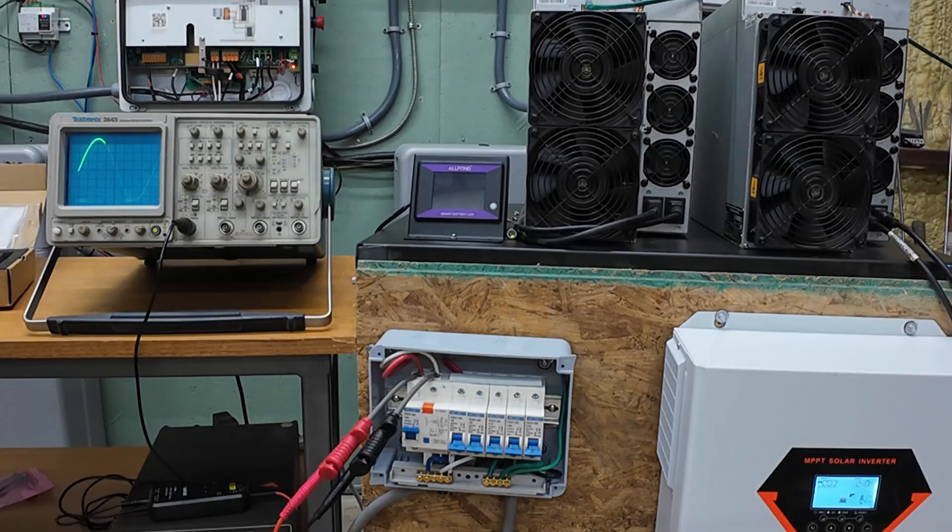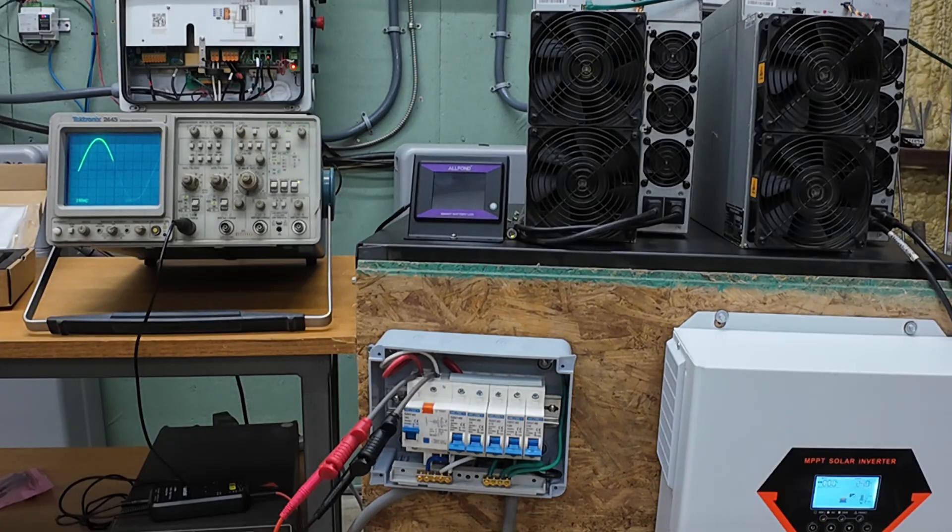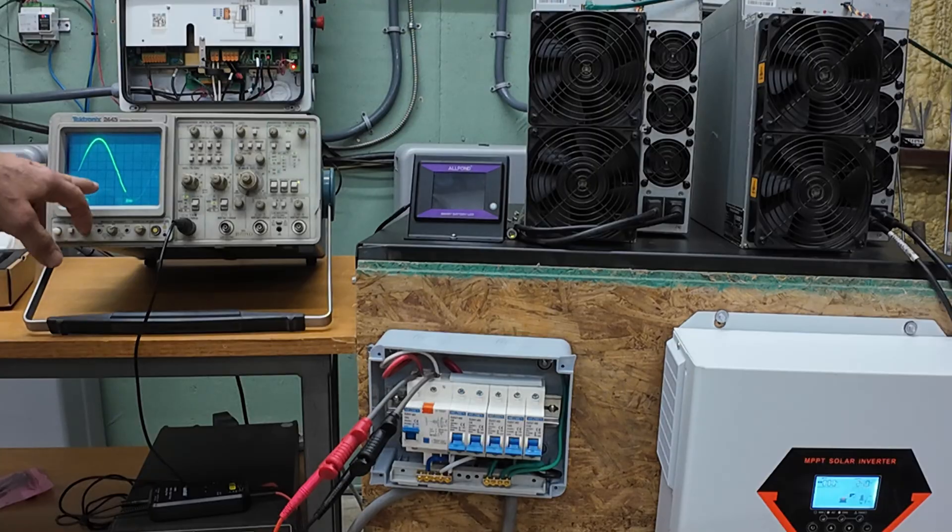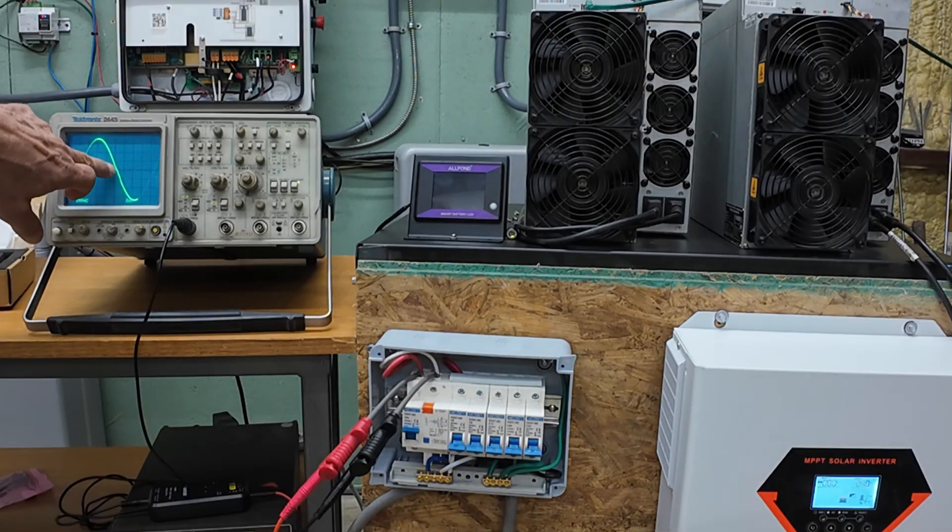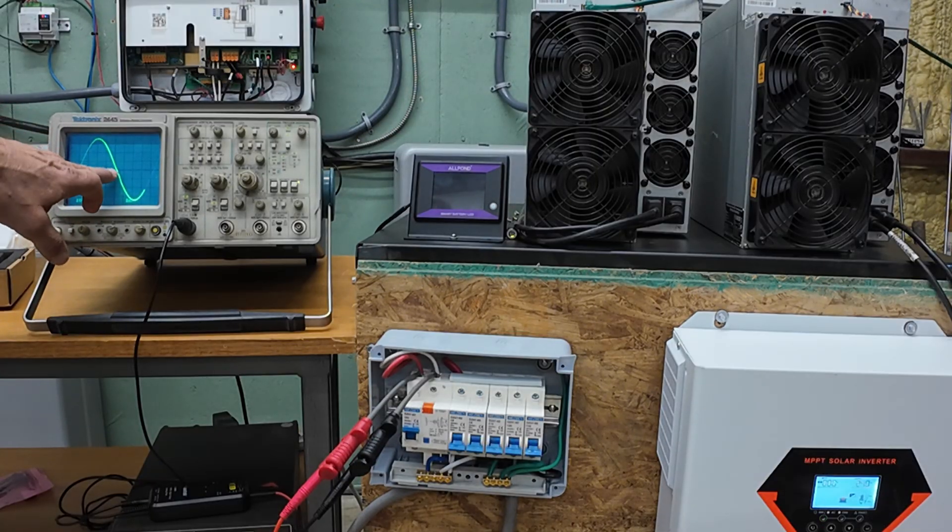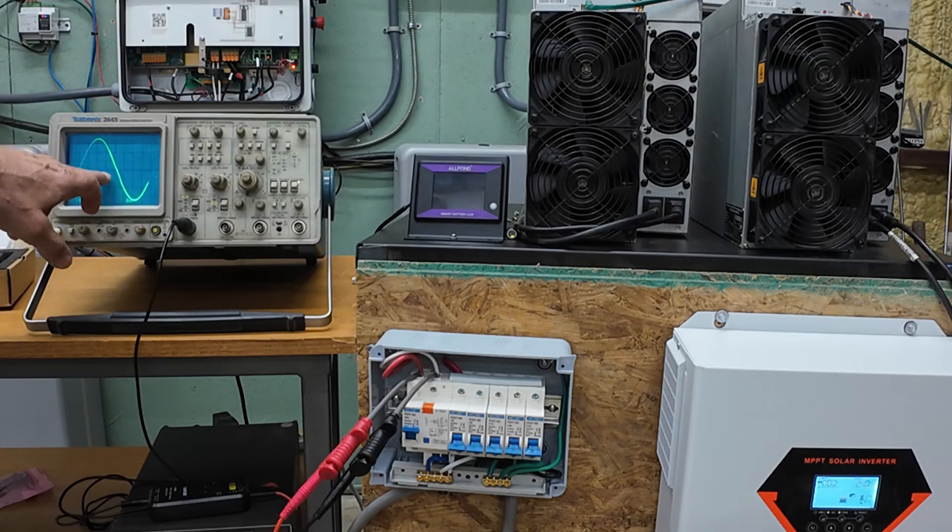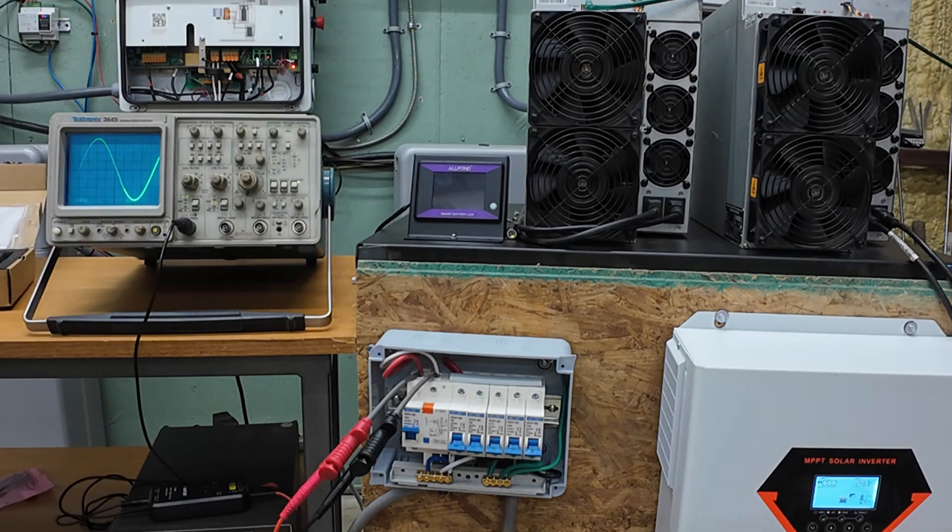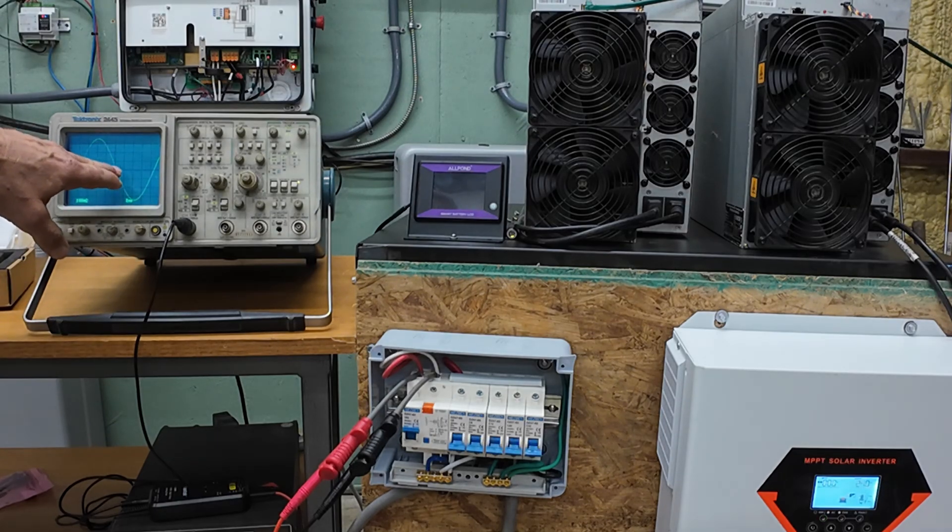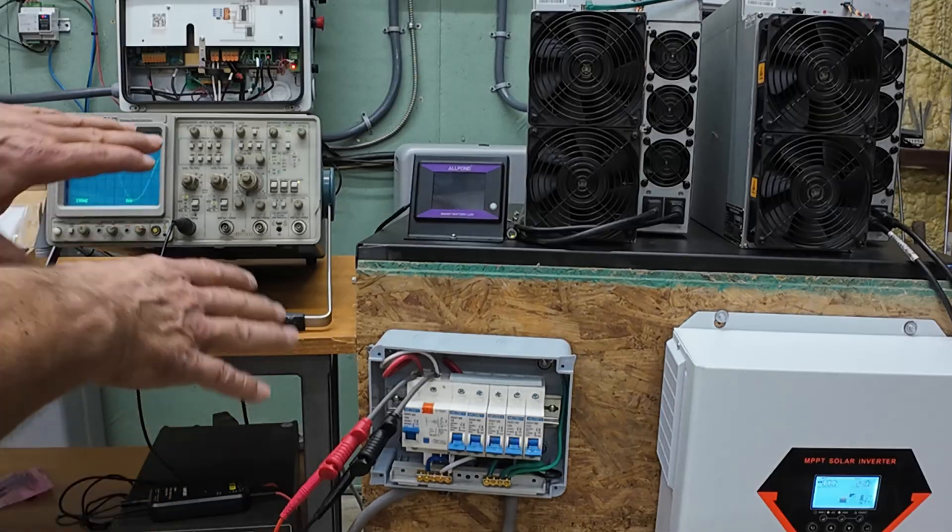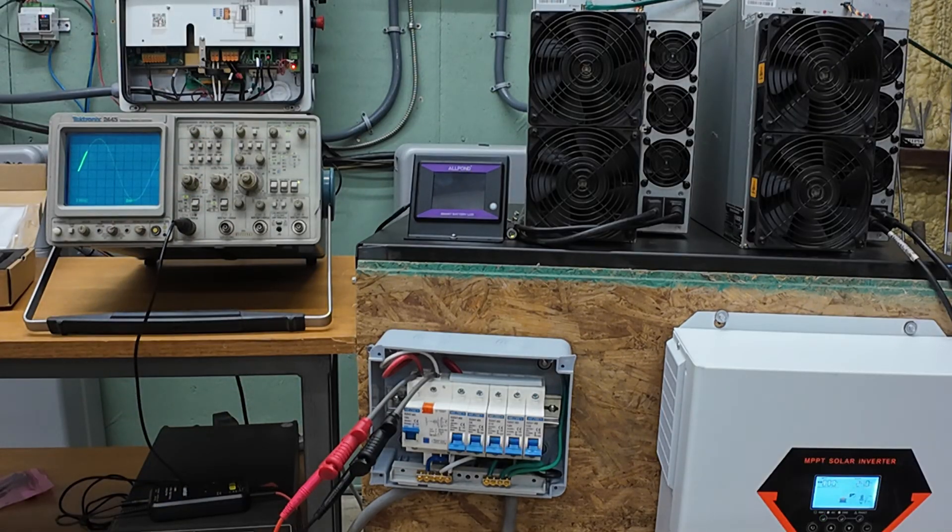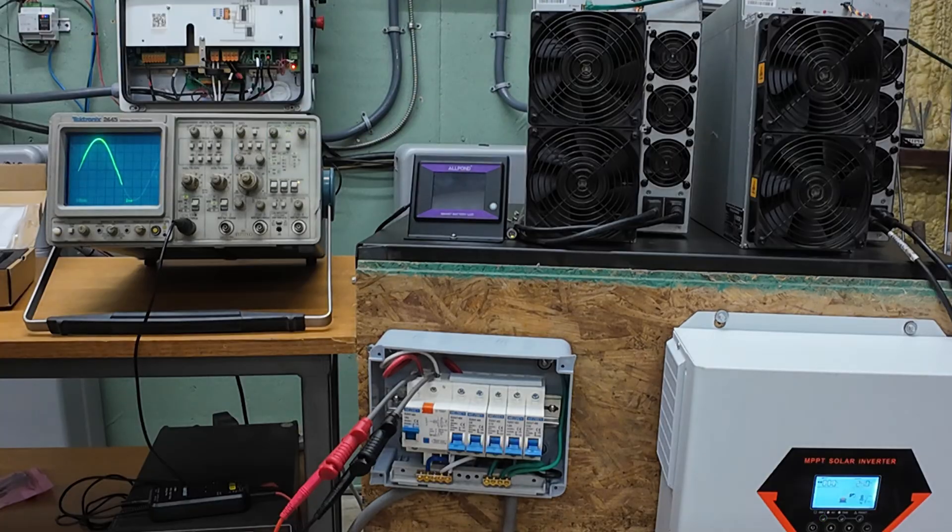All right, well there's the waveform at idle. That looks pretty clean. We've got a little hump here at the zero crossing point which is totally acceptable. That's where the IGBTs, two of the IGBTs shut off when it switches between the two sets of IGBTs. I guess that's it.